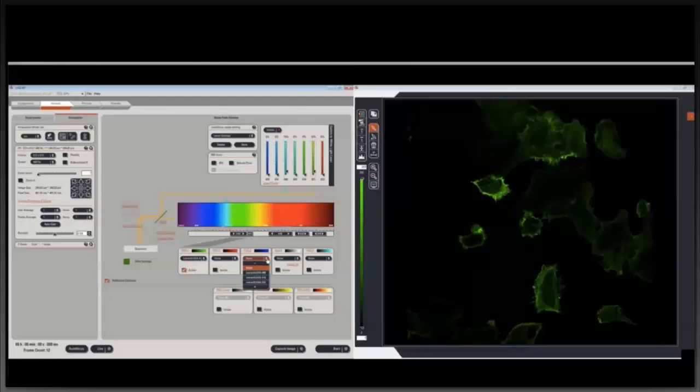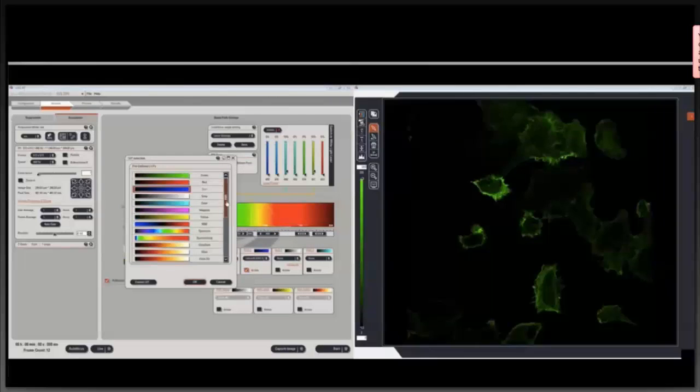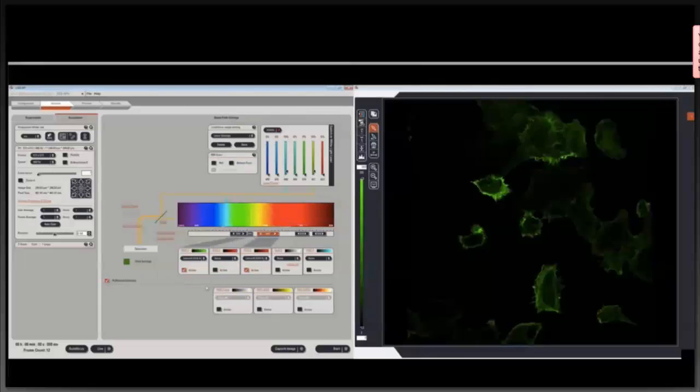A few things with this, first of all, is I'm going to get the spectrum up for the emission. And this is for Alexa 568, but it will be similar to cherry. So I can think about where I want my emission band to be. So if I activate my PMT, and I'm just going to move it so it covers a nice peak there. One more thing I'm going to do is change the lookup table to red. It's a lot easier to see than blue. Okay, and finally, do you remember from last time, we do need some gain.